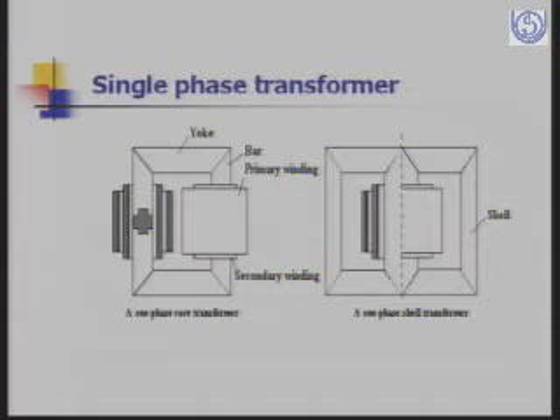So you can see in the slide the shell type and the core type transformer. The core type transformer is on your left hand side, and you can see that we have a core in which on the limb we have the winding, and in the shell type transformer the core is outside and the winding is in the center on the central limb. This is for a single phase transformer. Similarly, we can have a three-phase transformer, and this will be the structure of a three-phase core type transformer and a shell type transformer. You can see the difference of the core type and shell type transformer.